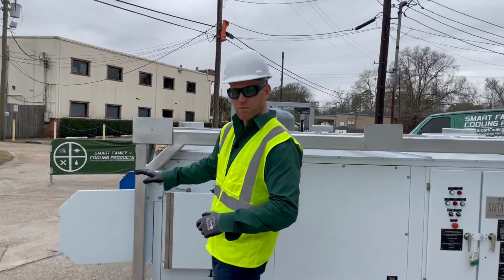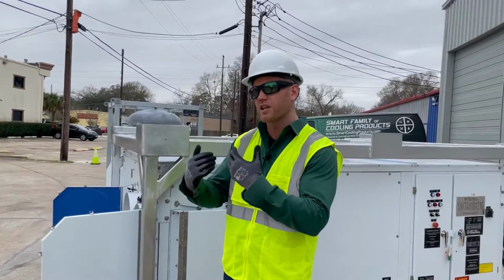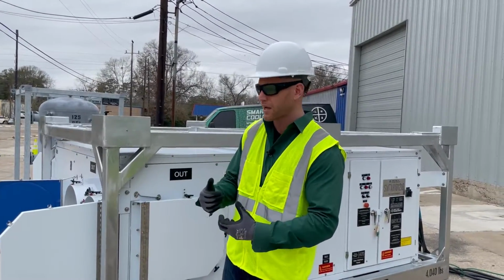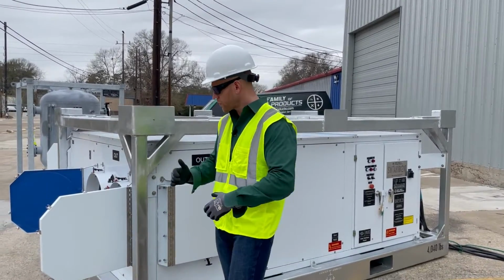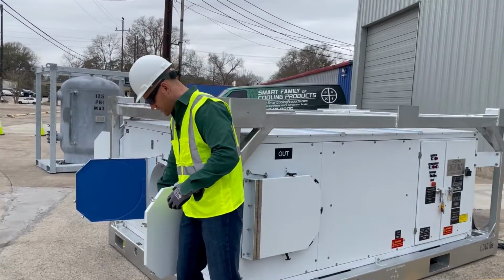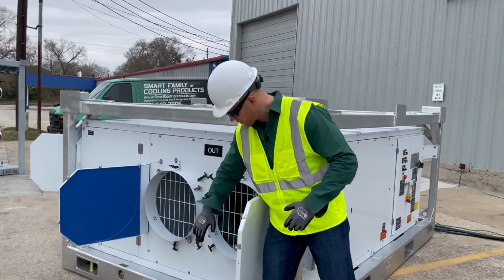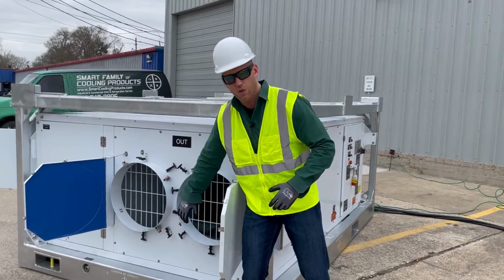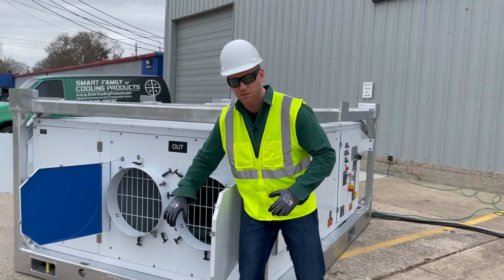Currently, this blower is in minimum position. That's typically where we want to start all air handling units and package units. We don't want to have so much force behind the air. But I can see even at minimum, you can see my sleeve. We're generating quite a bit of static pressure. Okay?